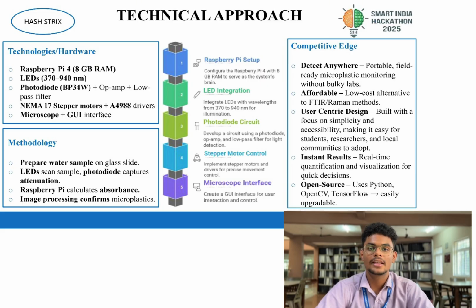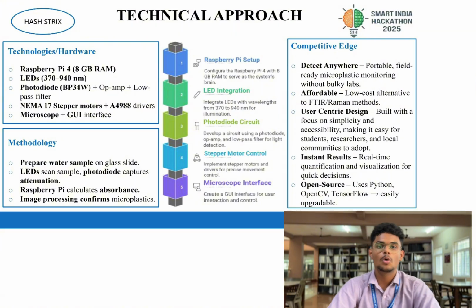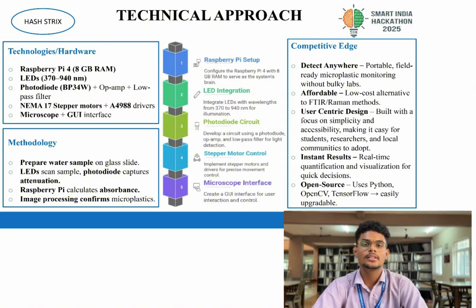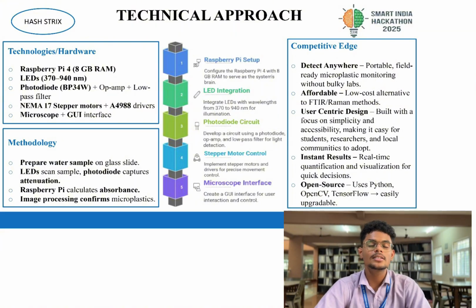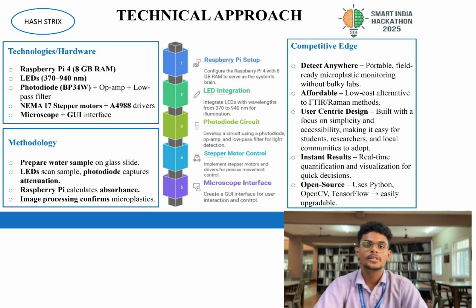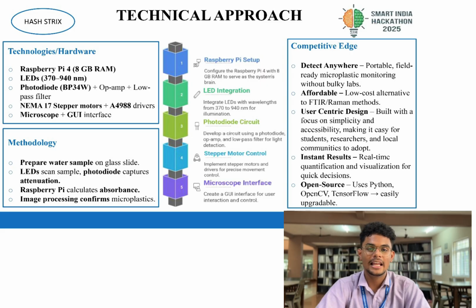When we keep a slide of water, we use a quartz cuvette. What this quartz cuvette does is, it doesn't absorb light as much as any other cuvettes or slides. So when we keep the water sample in this quartz cuvette, directly under the LEDs, the light bulbs, when we press activate, the light bulbs will release a light of certain wavelength to the device.